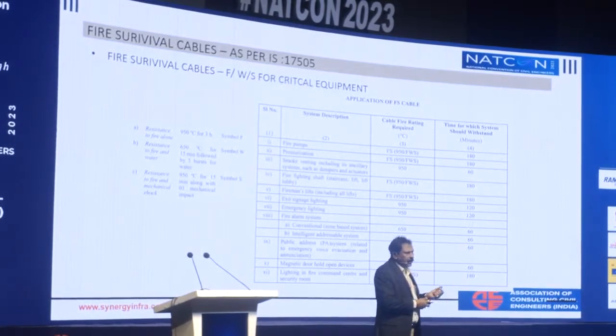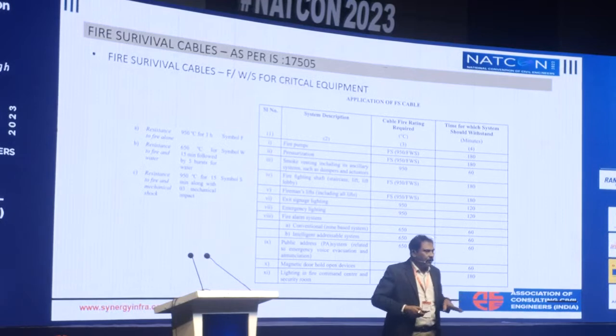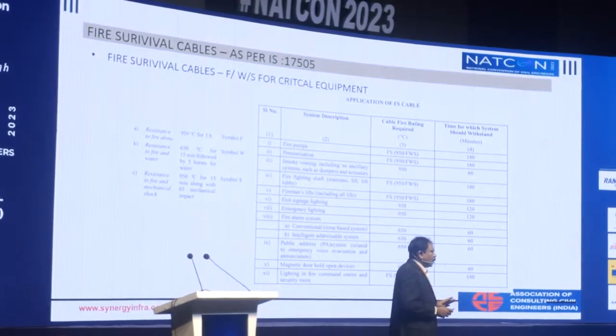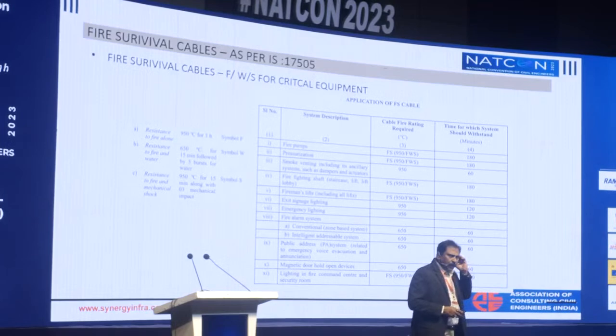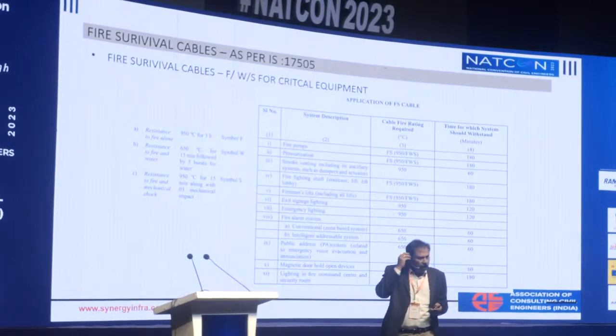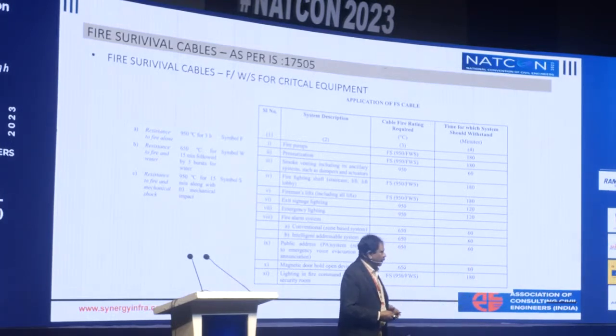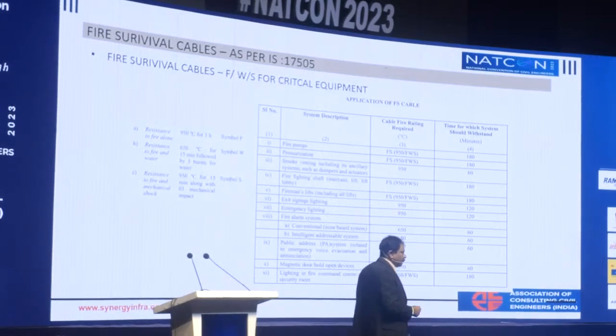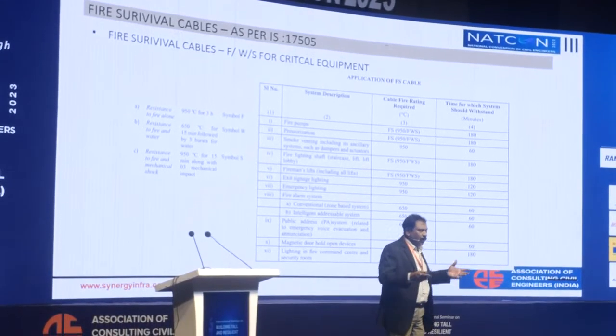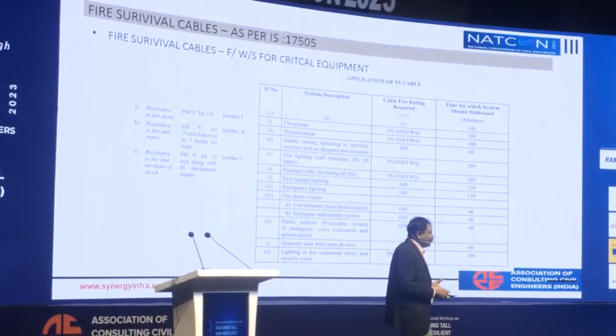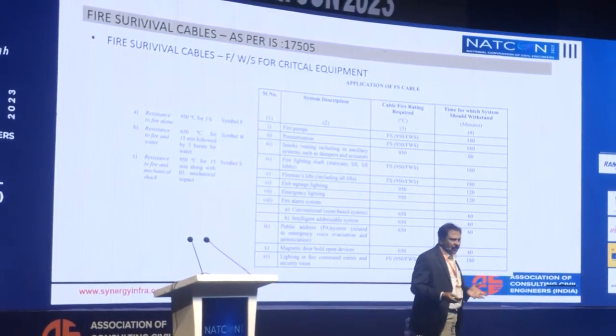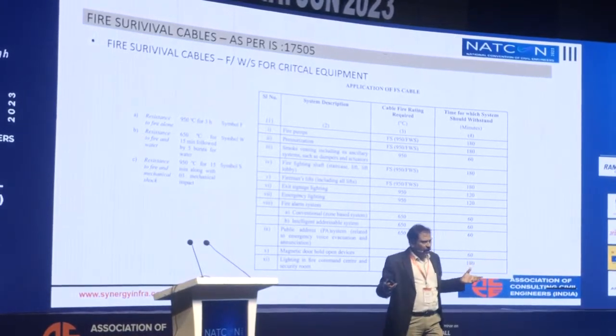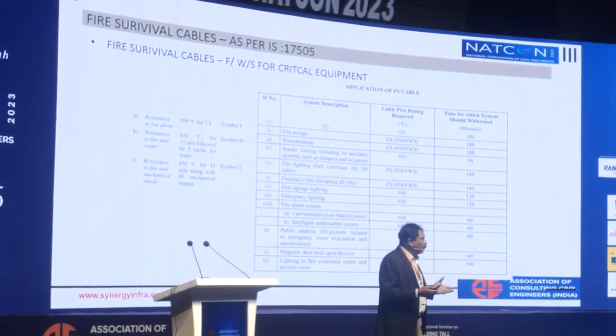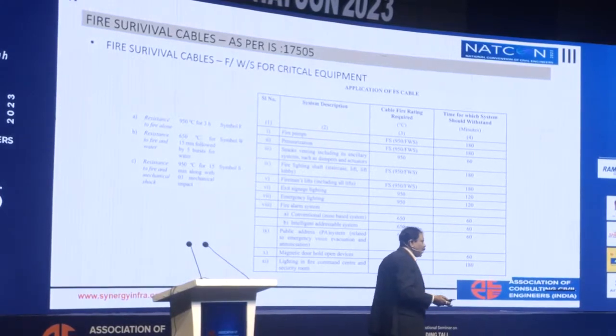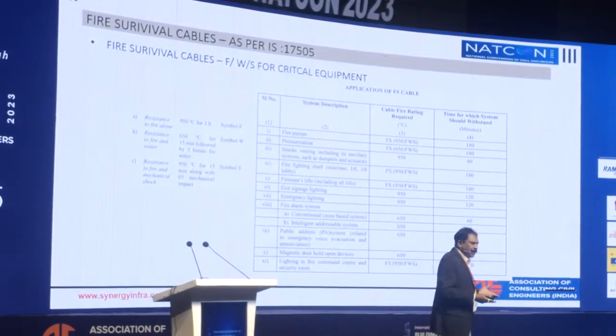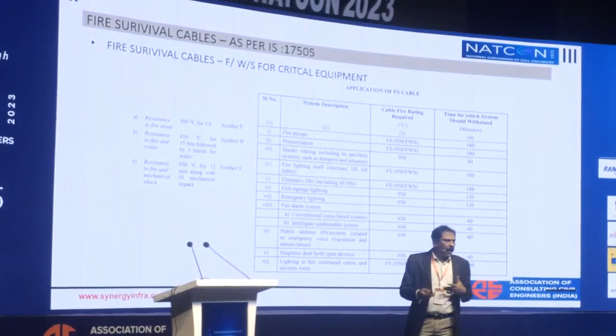Internationally, of course, our code does not recommend any kind of performance-based designs. But tall buildings cannot be done only on a prescriptive basis. It's very difficult. Look at our airport, for example, what code can you follow? You talk about compartmentation for any kind of assembly building with around 750 square meters of compartmentation. An airport is an open area with a lot of people around, and you would probably want a fire door at every 30-meter travel distance, an exit. It's not possible. So the only thing is you have to look at a performance-based approach.